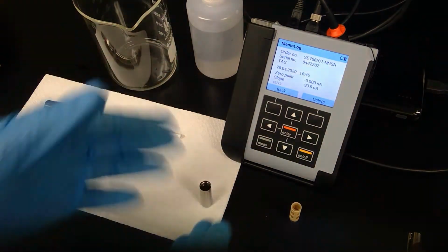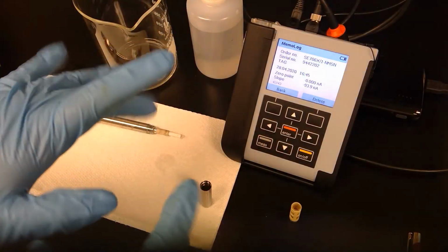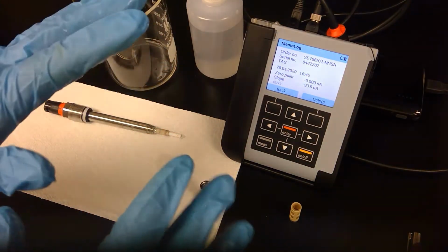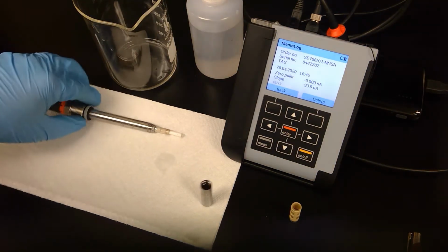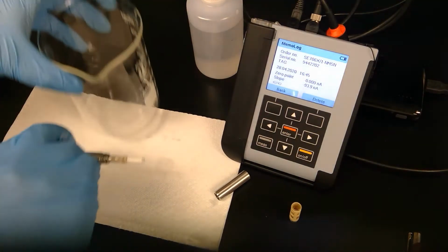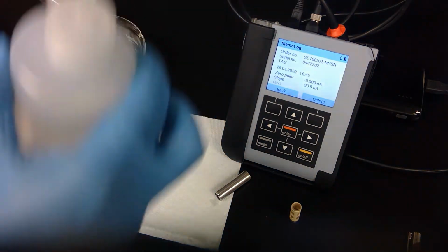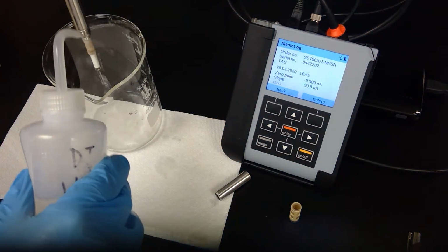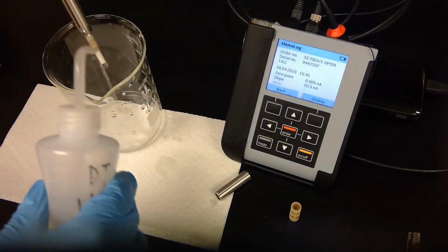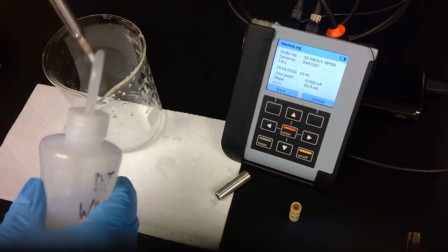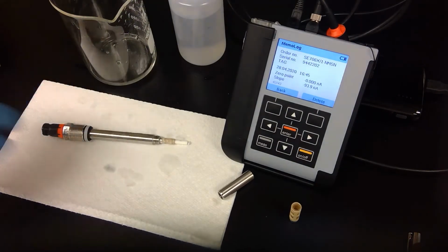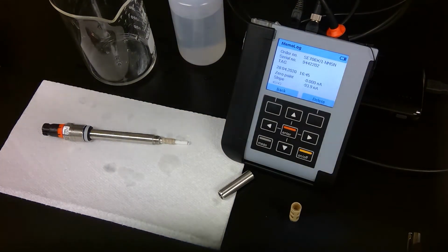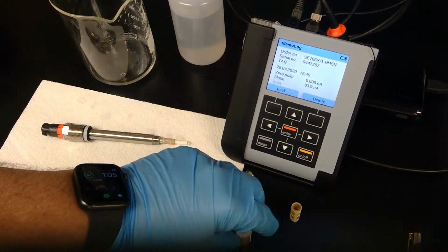Now you'll notice that I have gloves on, and that's because the electrolyte is basic. It's a pH of 13, so it can irritate your skin, so the gloves are just to prevent that. Next I take the electrode without the cap on, and I wash it with some DI water, clean the cathode off. Okay. And then we'll take this new membrane out in a second.